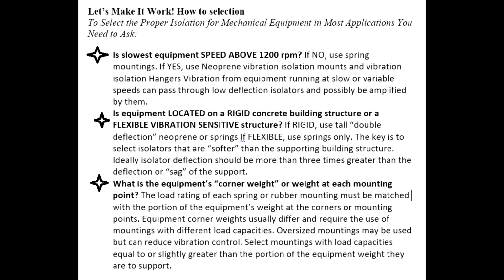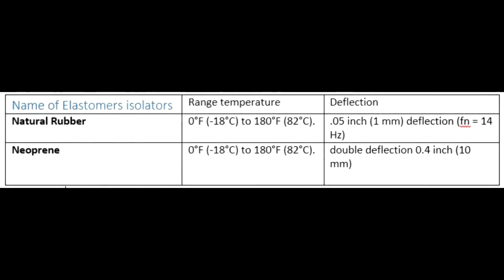What is the equipment corner weight, or weight at each mounting point? The load rating of each spring or rubber mounting must be matched with the portion of the equipment weight at the corner or mounting point. Equipment corner weights usually differ and require the use of mountings with different load capacities. Oversized mountings may be used but can reduce vibration control. Select mountings with load capacities equal to or slightly greater than the portion of the equipment's weight they are to support. Let's see some details and ranges of elastomeric isolators and spring isolators.